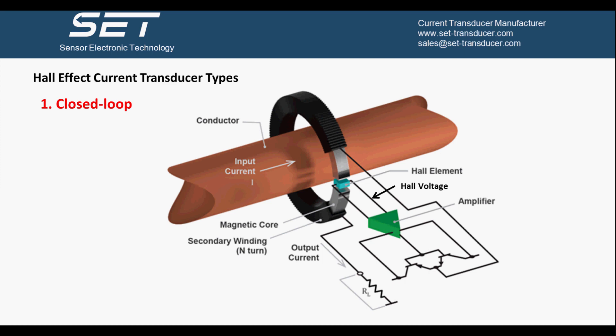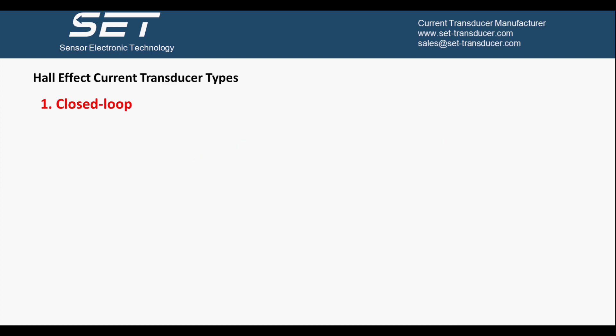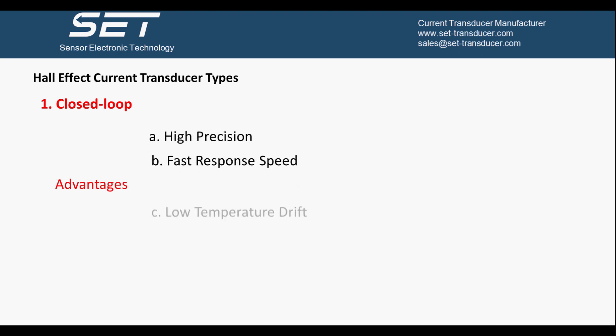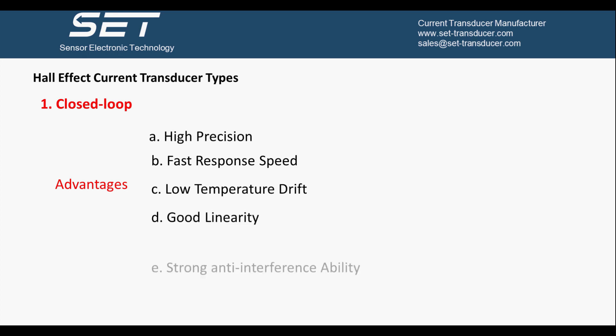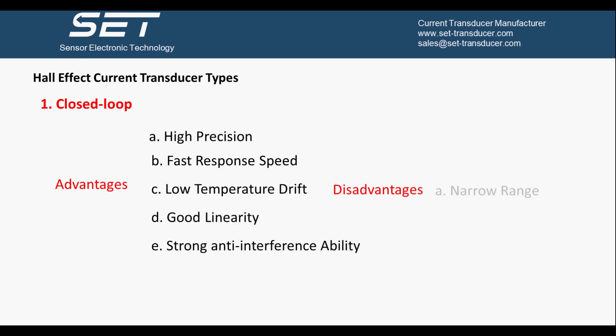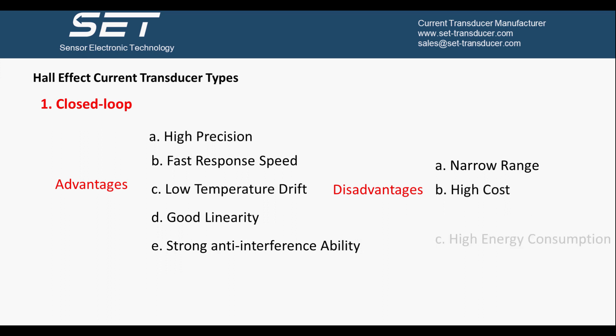When reaching this equilibrium state, the amplifier output current can represent the primary current. The advantages of the closed loop Hall current sensor are high precision, fast response speed, low temperature drift, good linearity, and strong anti-interference ability. The disadvantage is that the measurement range is narrow, and both cost and energy consumption are high.